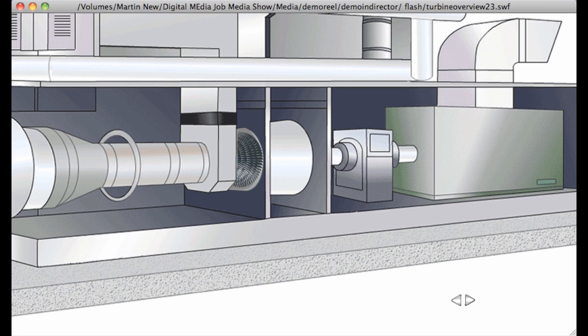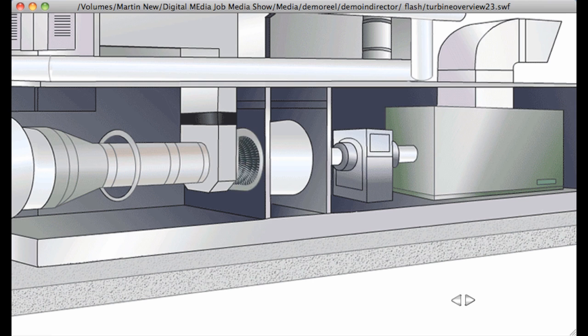The five rows or stages of spinning blades and their matching stationary or stator vanes compress the air. This compression generates some heat, so that when the air exits from the LPC, it can be at approximately 100 degrees Celsius when the engine is at full load. This varies depending on how much power the engine is producing.